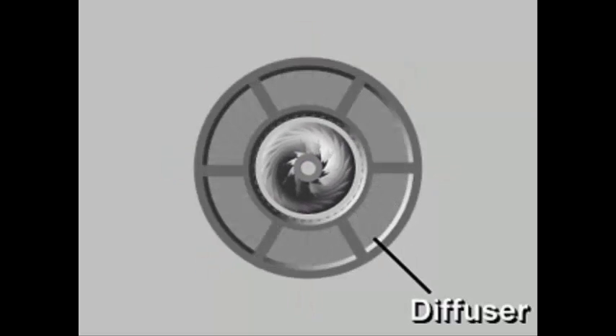To achieve the desired pressure increase, or compression, the vapor must be slowed down, converting its velocity pressure to static pressure. That's where the diffuser comes in. As high-velocity vapor moves radially outward through the diffuser, the flow area increases, slowing the vapor and increasing the static pressure. Some centrifugal models have diffusers with vanes or pipes which change flow direction and further slow the vapor.